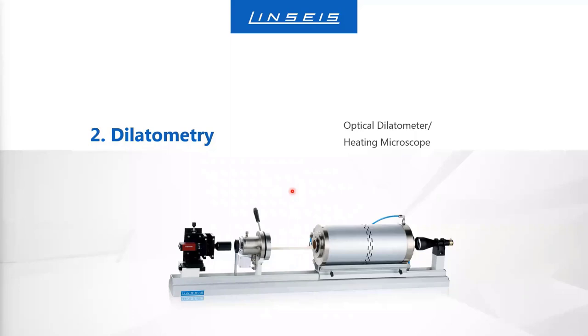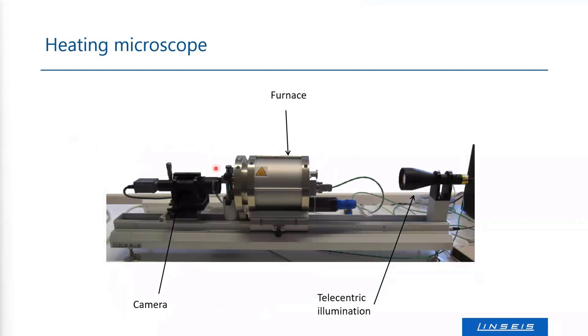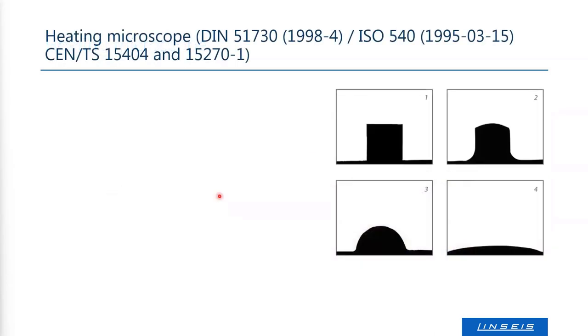The second type of dilatometers we have are optical dilatometers or heating microscopes. They consist of a furnace to heat samples to very high temperatures. A light source shines into the furnace, and on the other side there is a camera which records individual pictures or movies. The shadow images of the samples are recorded.